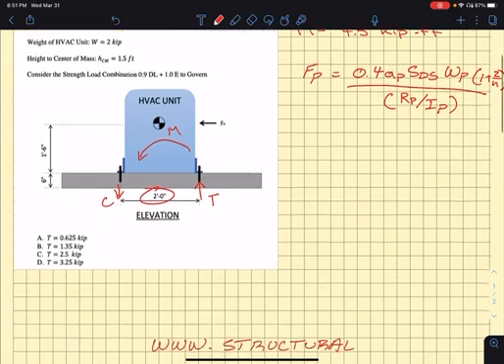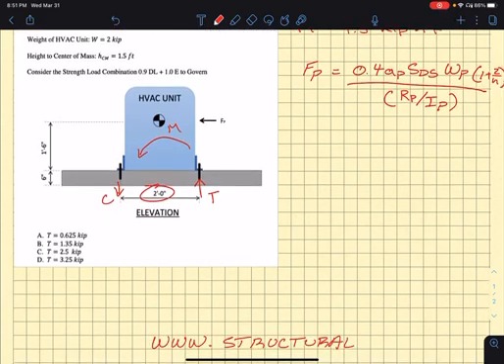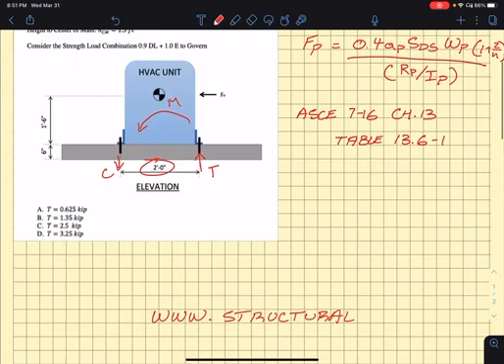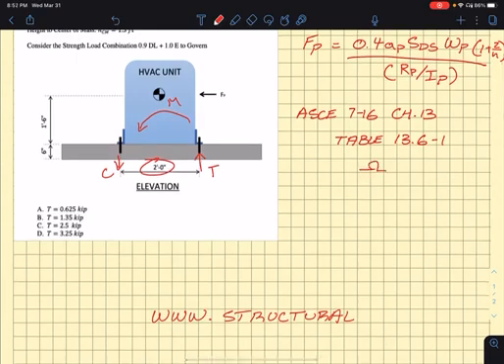So if you head over to the table at chapter 13, ASCE 7-16, table 13.6-1, and look up HVAC, you're going to find an omega factor, an overstrength factor of 2. All right, so now we can calculate the tension.